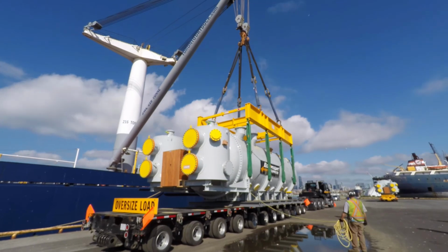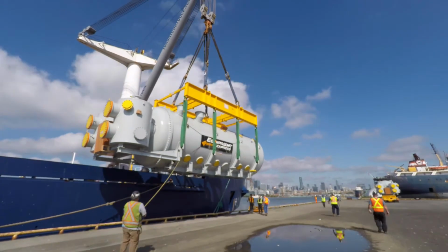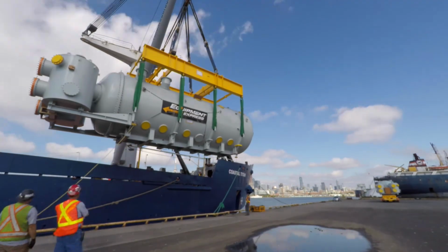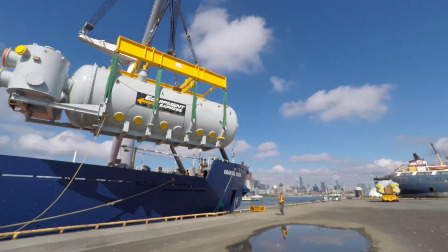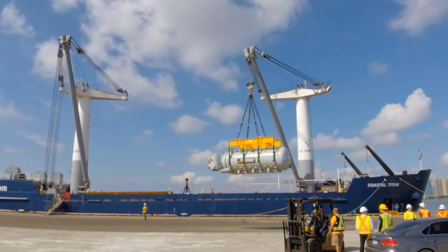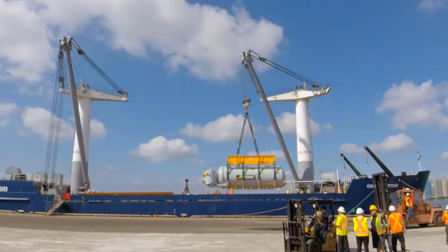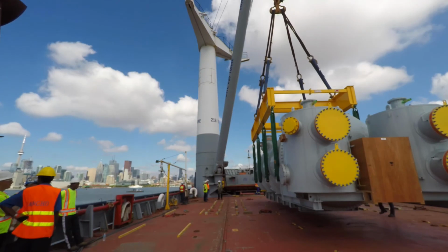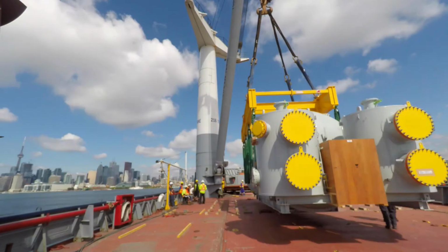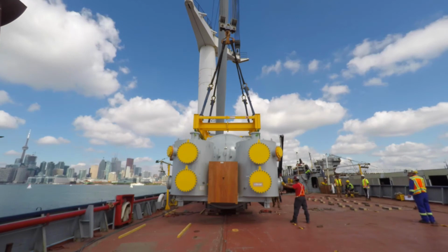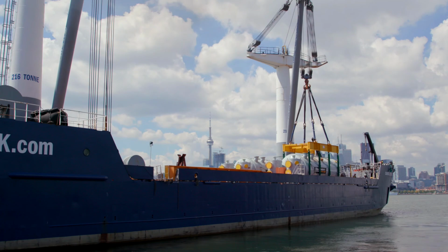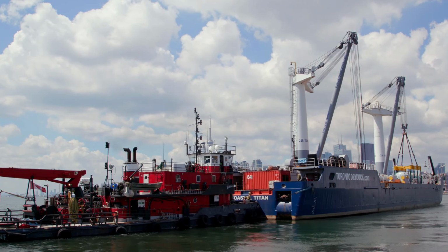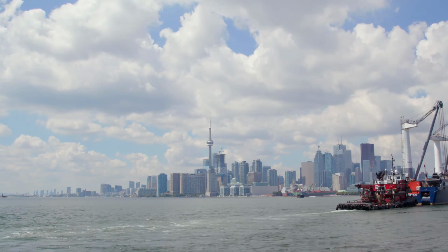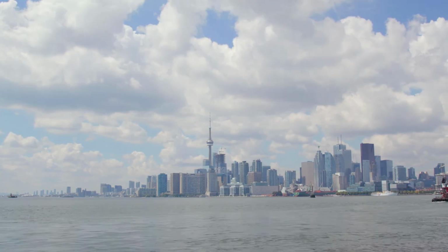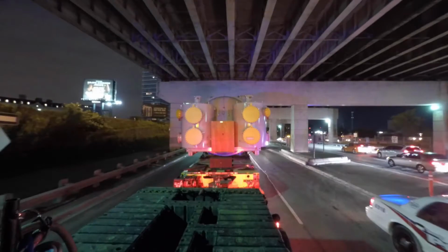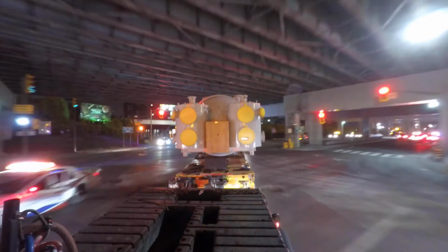Okay, so the transformers, as I mentioned, were delivered to the Port of Toronto, and they went into storage while we waited for the structure to be complete. Then we moved the transformers from their berth in the port to the transformer station. This time-lapse only takes a couple of minutes. The planning for this event took approximately 6 months, and a large part of it was due to the fact that each transformer tank weighs 155 tons, plus the associated equipment to roll it.